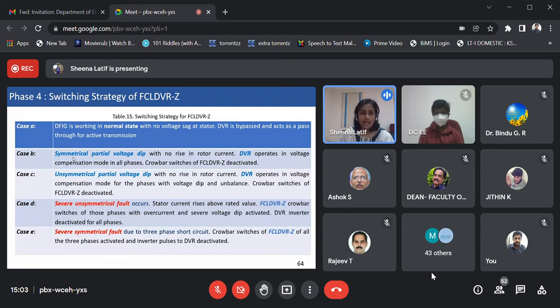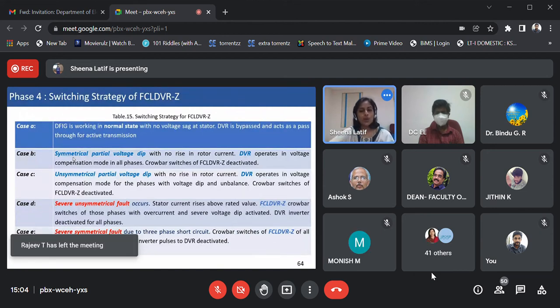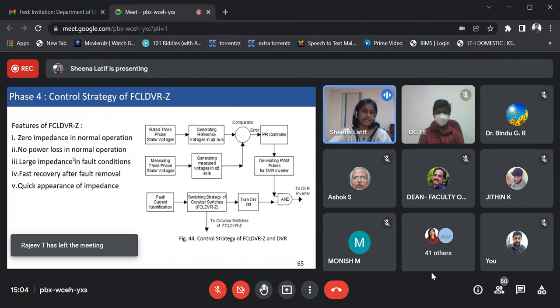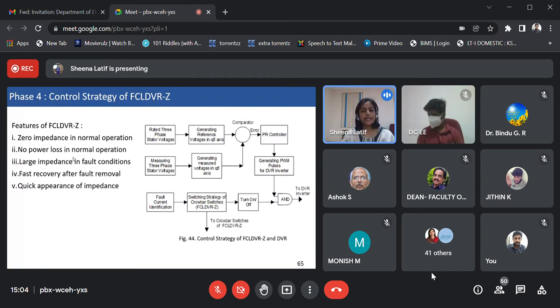If there is a severe unsymmetrical fault which causes an overcurrent in the rotor, then the FCL DVR impedance crowbars of those phases which have overcurrent and severe voltage dip will be activated, while the DVR inverters for those phases will be deactivated. And in a severe symmetrical fault condition, all three phases of the FCL DVR impedance crowbar switches will be activated and the DVR pulses will be deactivated. So this is implemented in the control strategy of the FCL DVR impedance and DVR method.